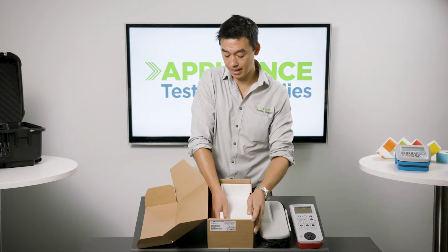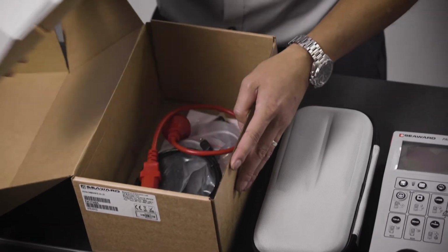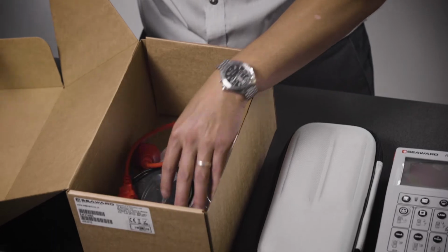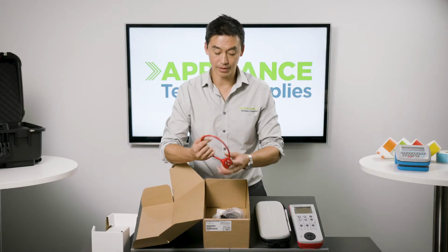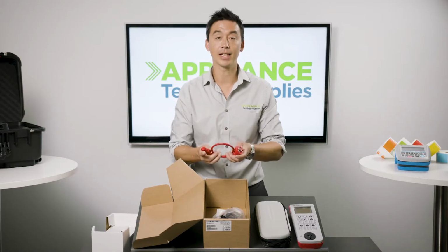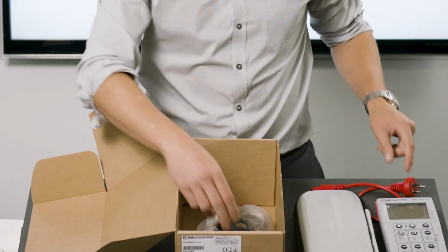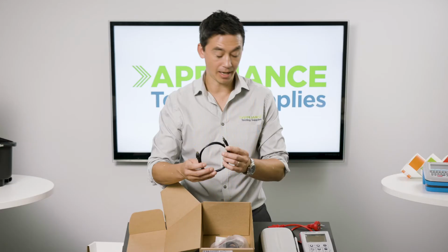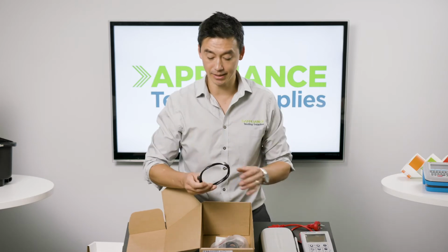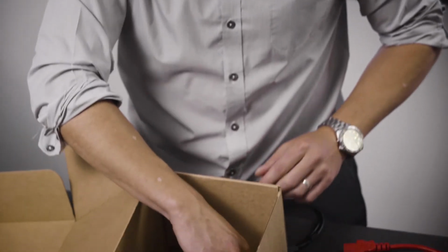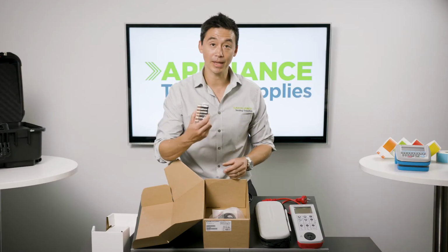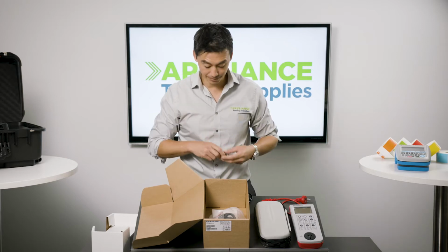Underneath the cardboard casing here, we have all the test leads and download leads you need. So we've got the red IEC lead, that's for your extension leads, power boards and the like. We've got the USB download lead. This machine does have memory, so you need to get the data off the machine using this. We have a set of 6 alkaline batteries, which are easily replaceable when these things go flat.